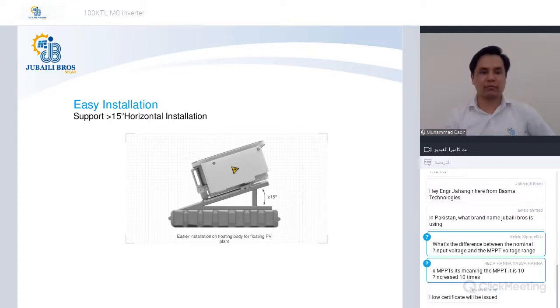Easy installation. The Huawei 100 kilowatt can be installed at 15 degrees from the horizontal level. This gives you a lot of flexibility for using it in multiple scenarios. This concept comes from installing the inverter in floating PV plants, having solar panels on a lake or a river. You can install the solar inverter there, and having a lesser height by installing it at 15 degrees from the ground level, it casts less shadow, and therefore it gives you more space for installing the solar panels. The previous inverters of Huawei supported up to 15 degrees from the vertical level, but the flexibility of the 100 KTL is even more.